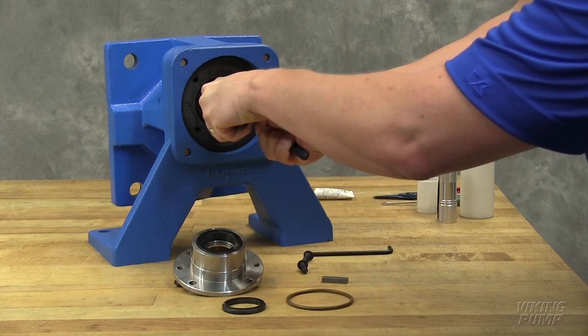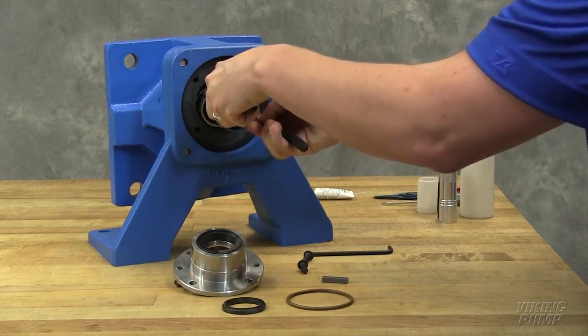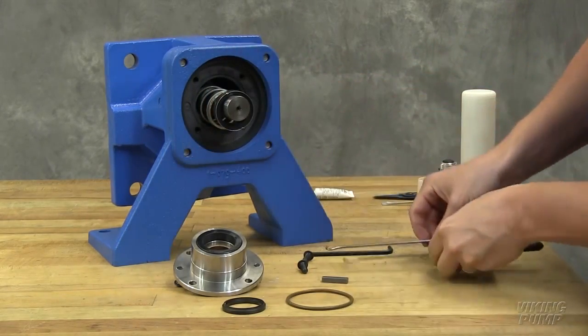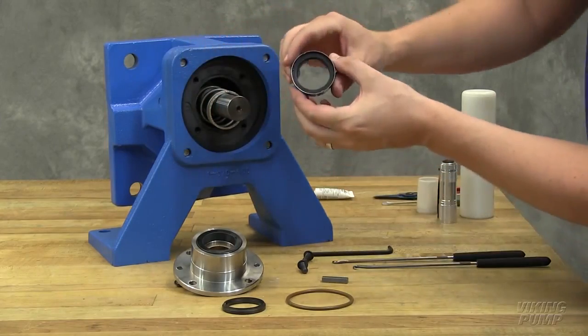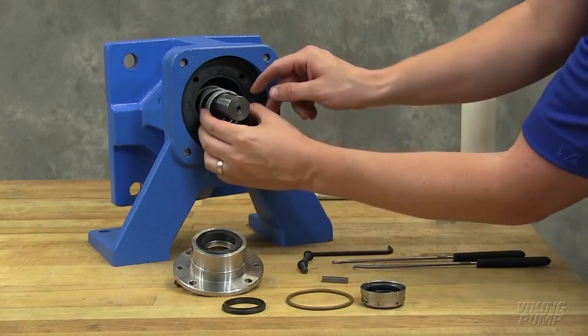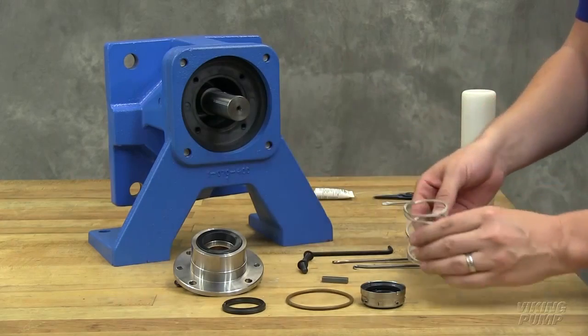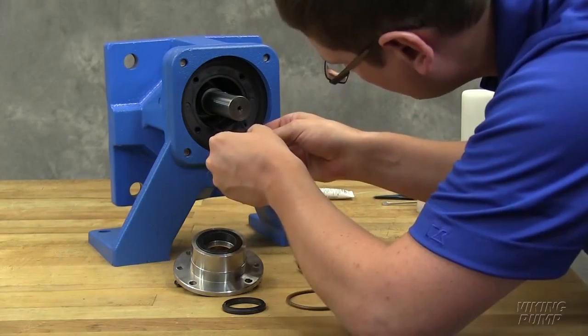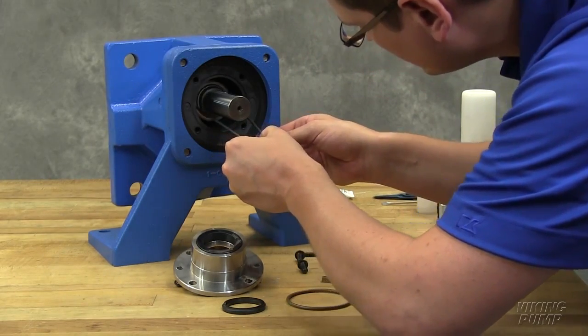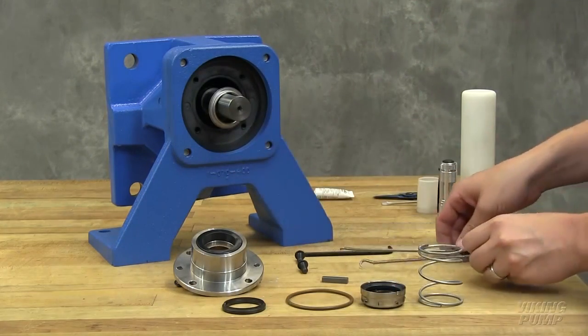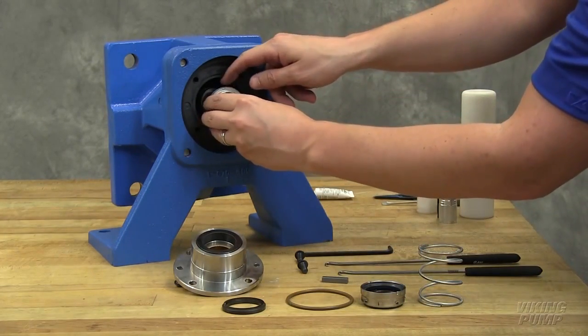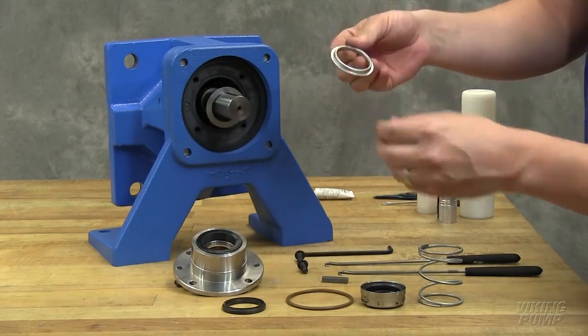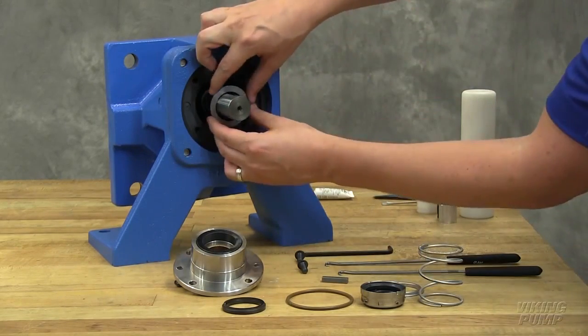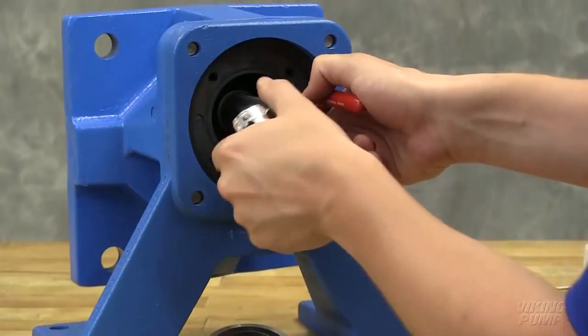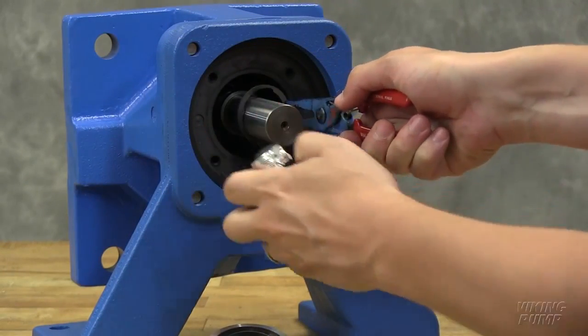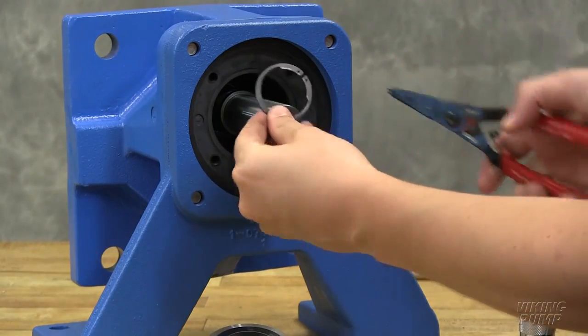If the seal cannot be removed, use a piece of PVC pipe to push the rotating part down the shaft and into the pump to break the grip of the bellows on the shaft. Then use the picks to pull the mechanical seal out. Remove the seal spacer. Use the snap ring pliers to remove the retaining ring on the shaft.